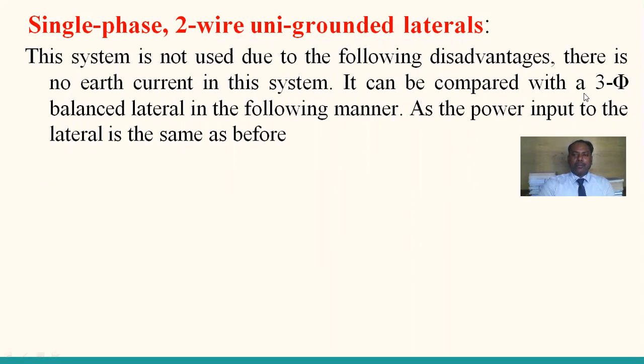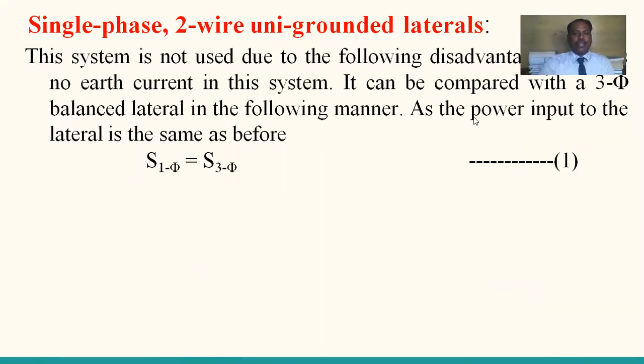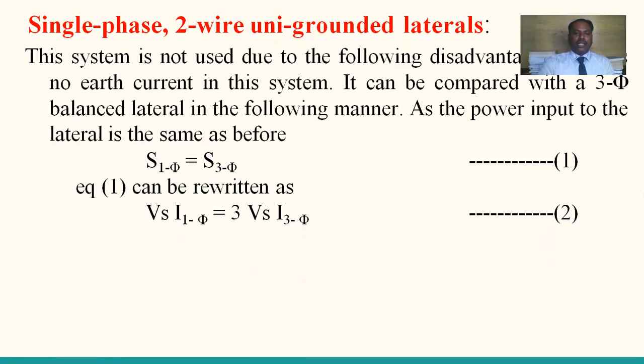So it can be compared with a three-phase balanced lateral in the following manner. The power input to the lateral is the same as before, so the loads of both systems are the same. See, S single phase is equal to S three phase, and this is a three-phase balanced system. It is a single phase two-wire uni-grounded system, where one conductor is grounded. So Vs into I single phase is equal to 3 Vs into I three phase. This is equation number 2.